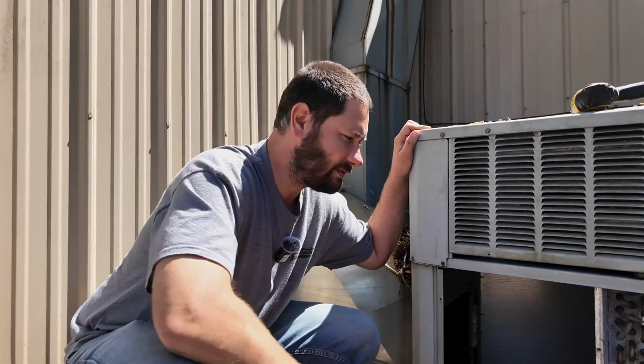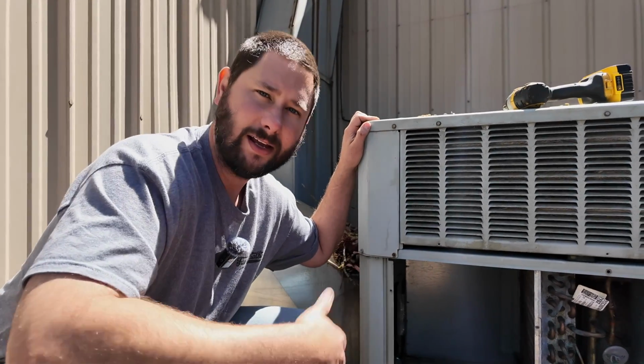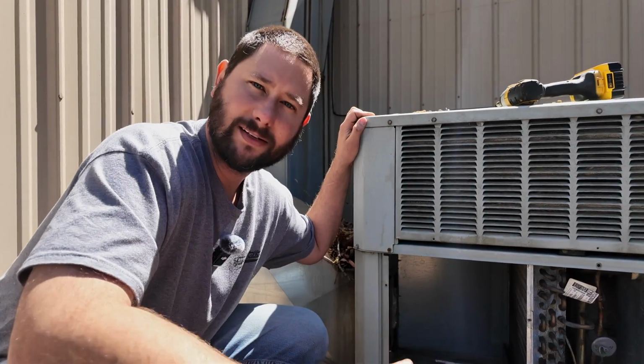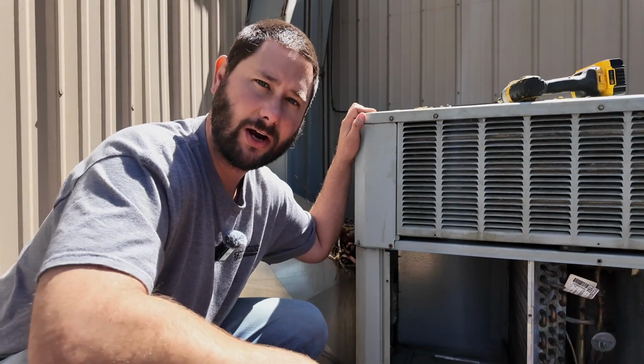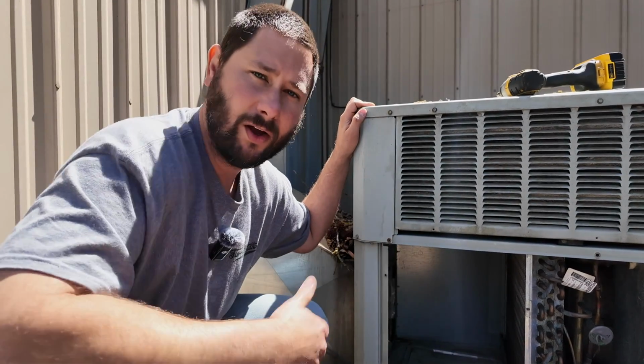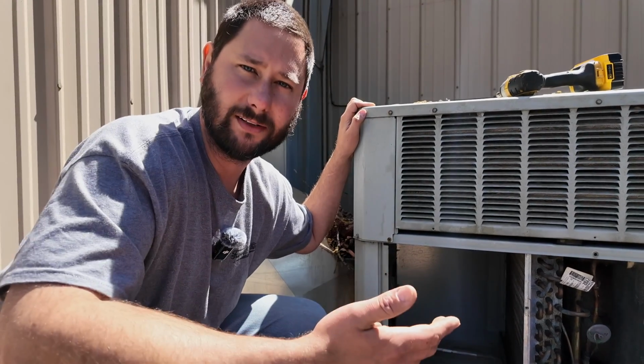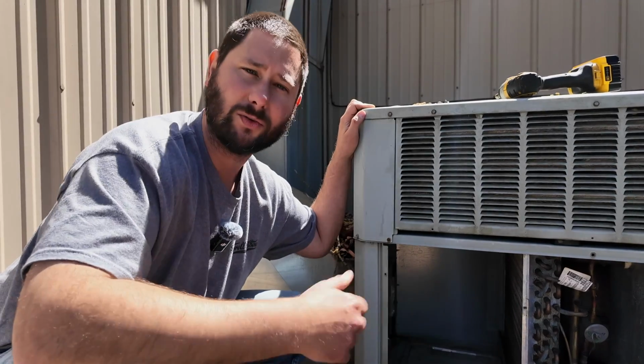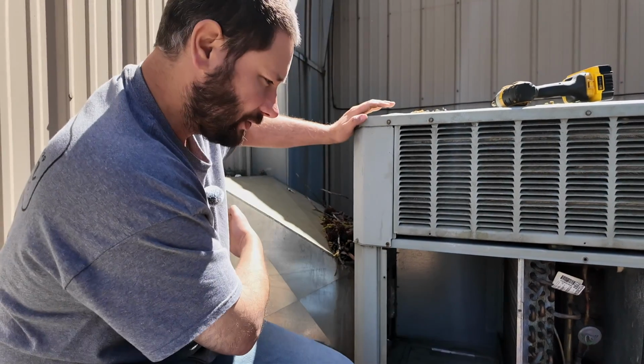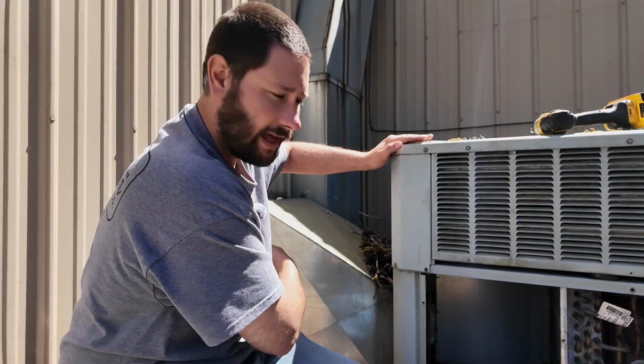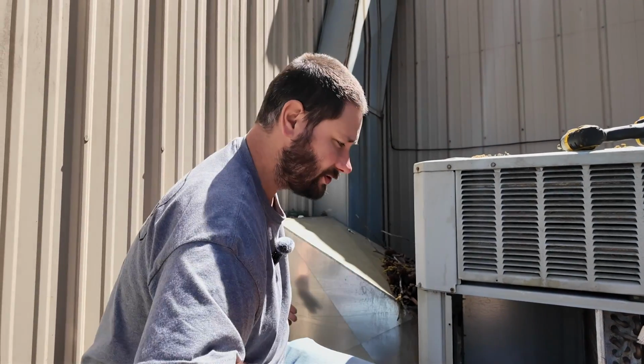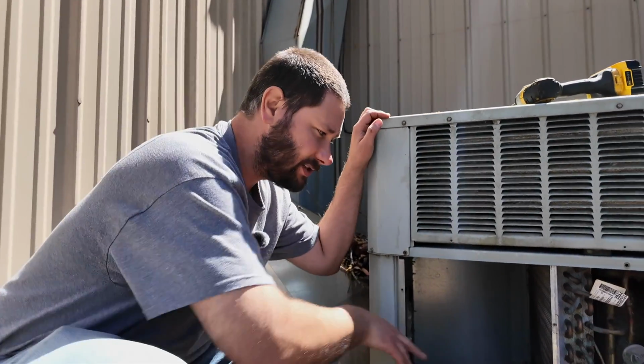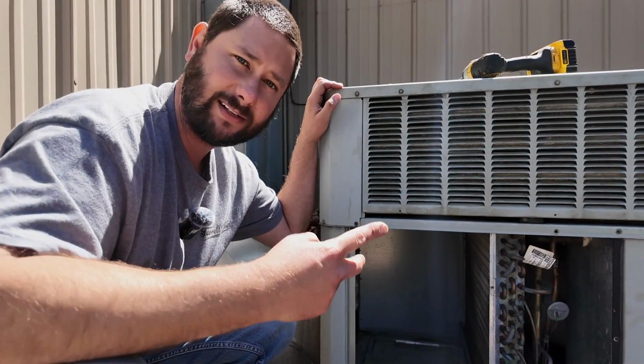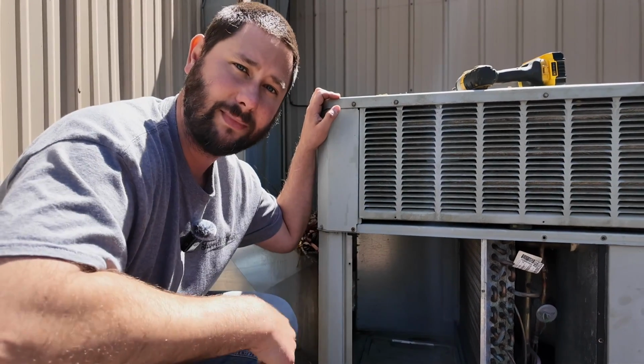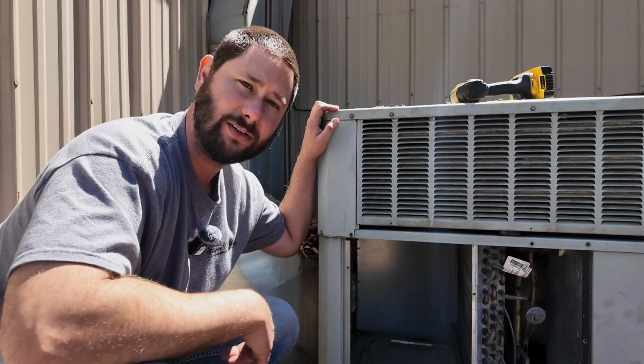There's a couple causes for this coil being dirty. One is holes in the ductwork. Maybe it's in the crawl space, sucking in dirt. That dirt goes into the coil. Or maybe they're not changing their filter regularly. Maybe there's no filter in the actual return grill. Air goes in the filter, then goes through the return trunk, and then into this coil. So those two things can cause this coil to get really dirty. Make sure you change the filter, make sure you seal the ductwork.